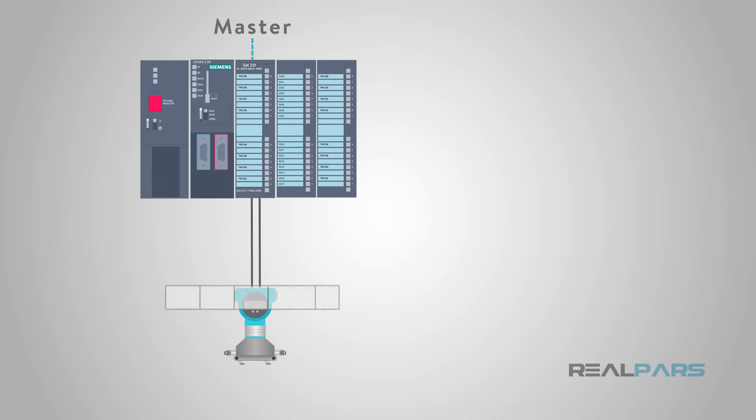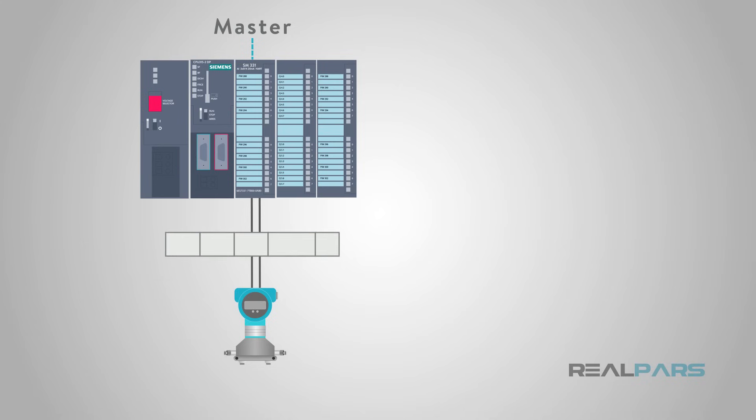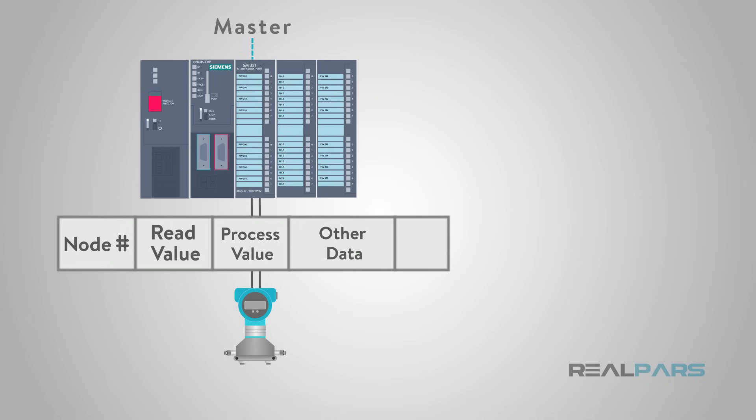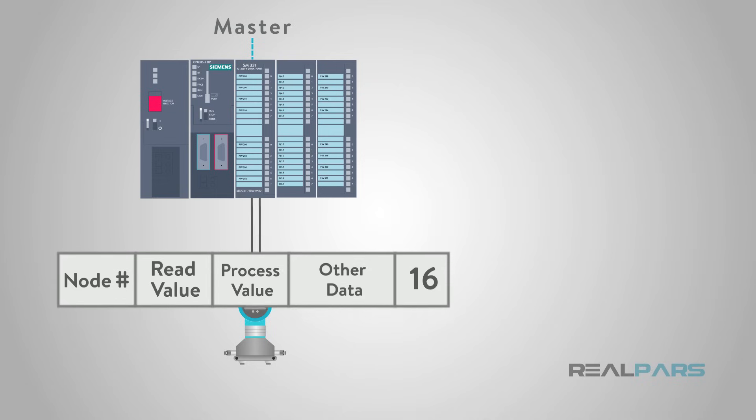Each message from the master includes the request type, such as send measurement value, the node number of the sensor the message is intended for, and any data that needs to be transmitted to the sensor, like a new value for the upper range limit.